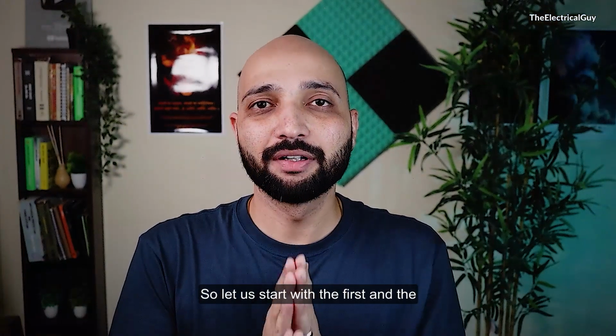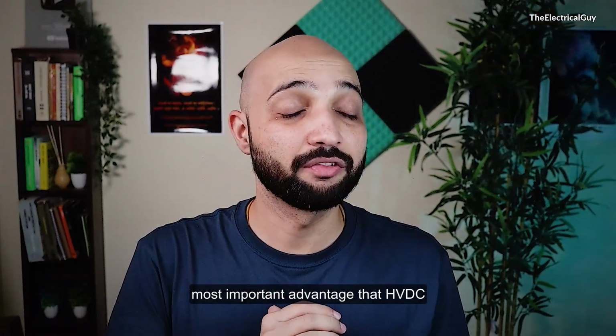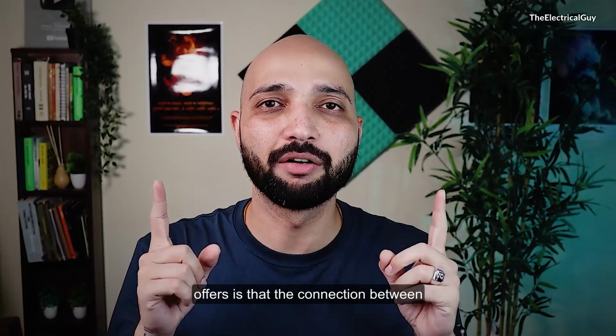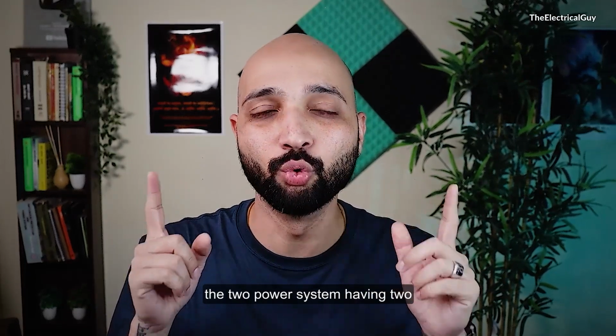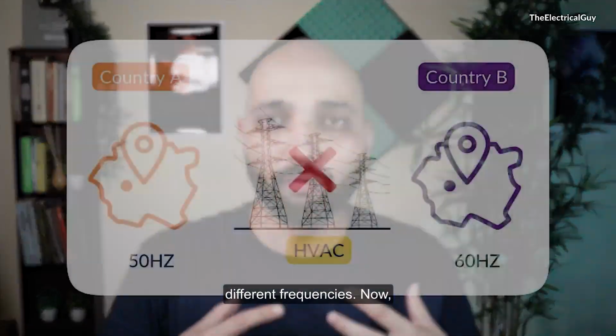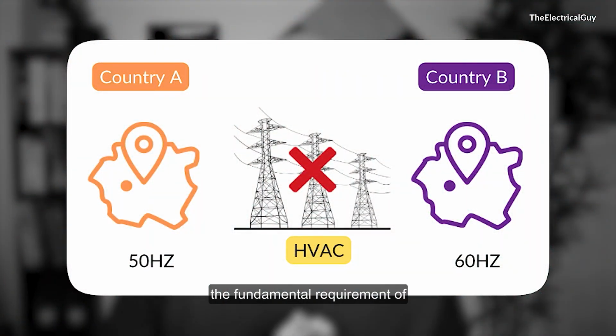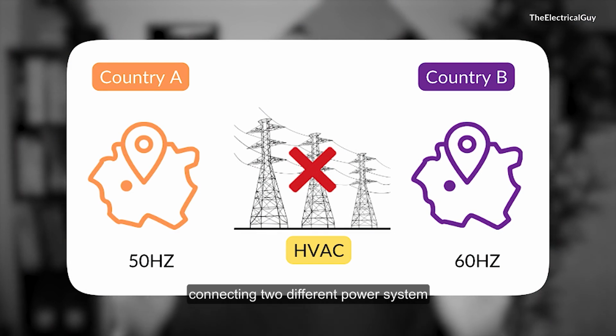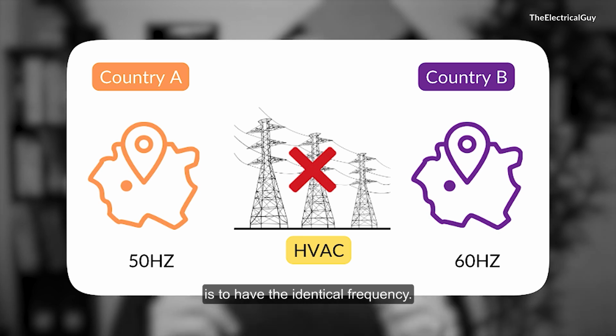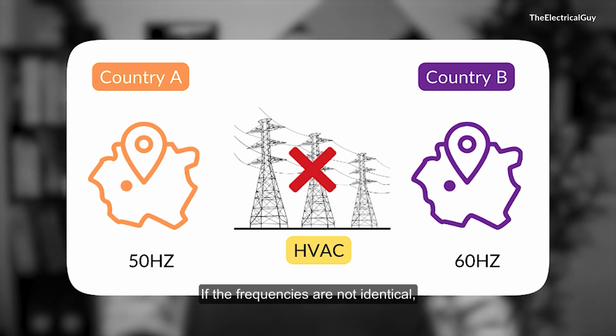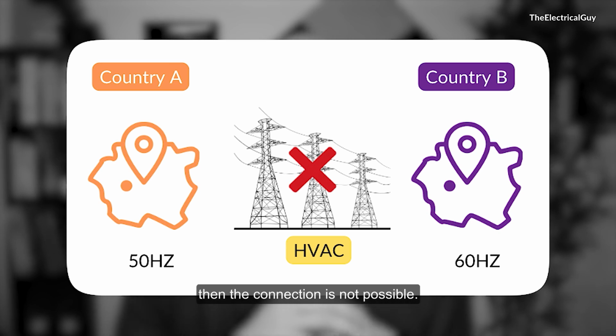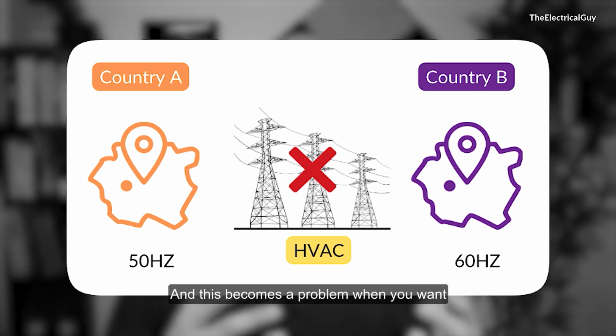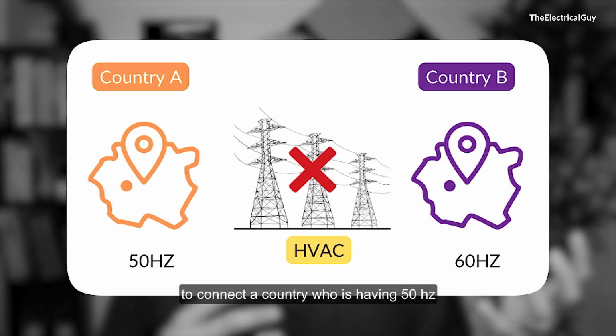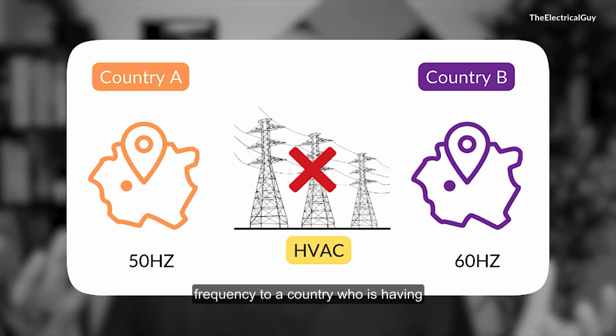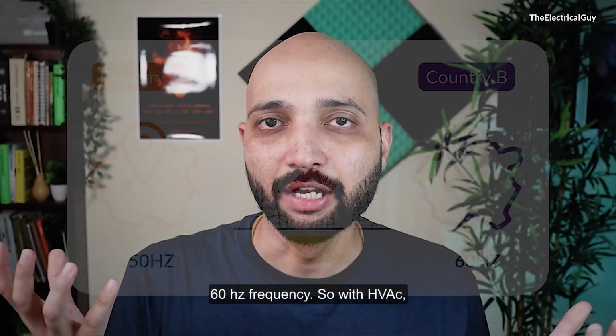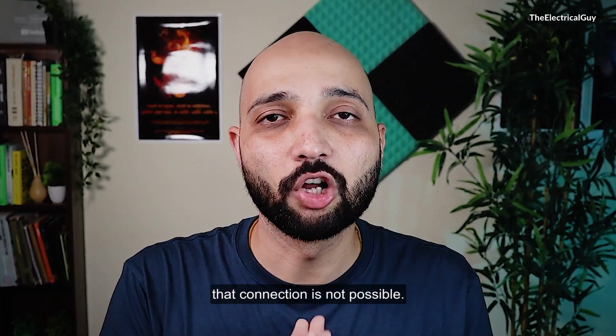The first and most important advantage that HVDC offers is the connection between two power systems having two different frequencies. With HVAC, the fundamental requirement of connecting two different power systems is to have identical frequency. If the frequencies are not identical, the connection is not possible. This becomes a problem when you want to connect a country having 50 hertz frequency to a country having 60 hertz frequency. So with HVAC, that connection is not possible.